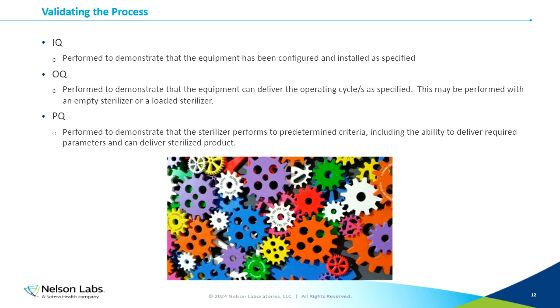So now, when we're validating the process, we have three different main considerations. I'm going to get into mostly the third consideration, but I want to mention the first two as well. These are often performed by the sterilizer manufacturer when those sterilizers are sold to the user. So the first one is the installation qualification, or IQ. We perform that to demonstrate that the equipment has been configured and installed as specified. As I mentioned, that's often performed by the sterilizer manufacturer.